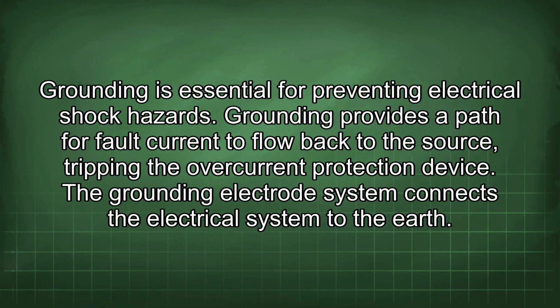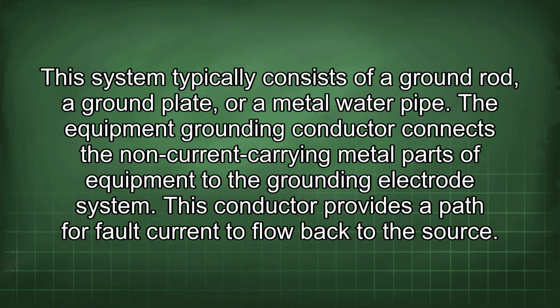Grounding is essential for preventing electrical shock hazards. Grounding provides a path for fault current to flow back to the source, tripping the overcurrent protection device. The grounding electrode system connects the electrical system to the earth. This system typically consists of a ground rod, a ground plate, or a metal water pipe. The equipment grounding conductor connects the non-current carrying metal parts of equipment to the grounding electrode system. This conductor provides a path for fault current to flow back to the source.